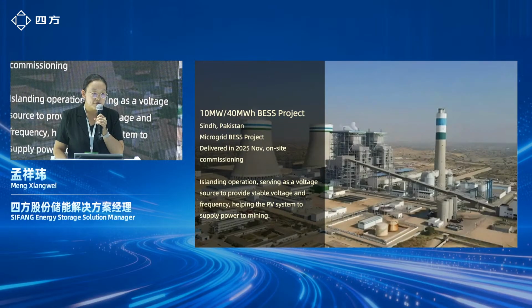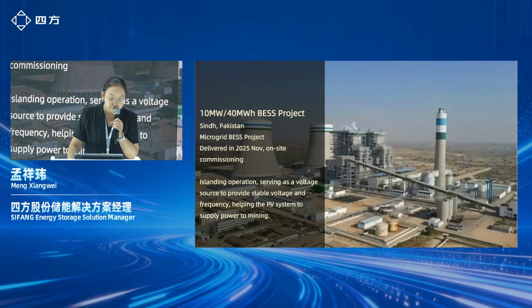Here is one of our overseas grid-forming projects. It's a 10 megawatt and 40 megawatt hour grid-forming BESS project in Pakistan. And in this project, the PCS can maintain the full load capacity under 50 centigrade, and it can provide islanding operation to the load, to the mining load.